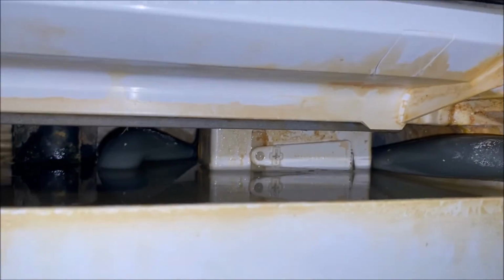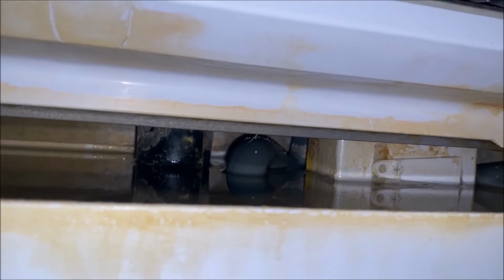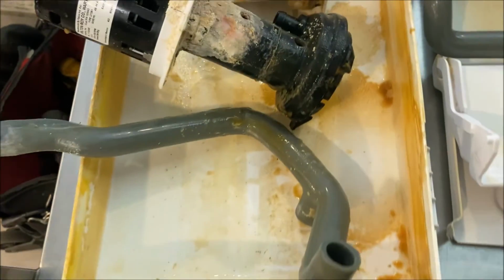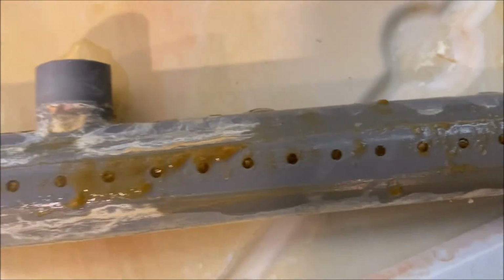There's our float switch, there's our pump. They are absolutely filthy. So let's go ahead and pull everything apart, get everything out. In this case, we have to pull everything out because it is filthy, as you can see. Water distribution manifold is plugged, and here's our float switch that I was talking about.